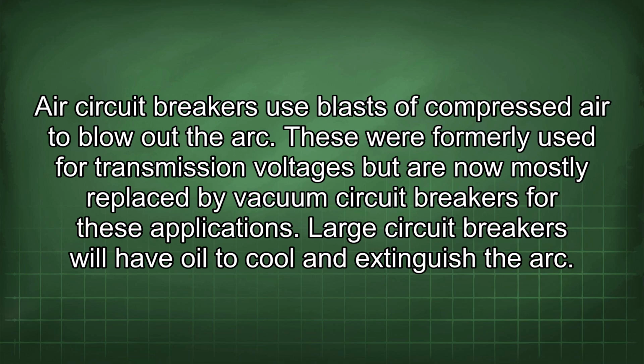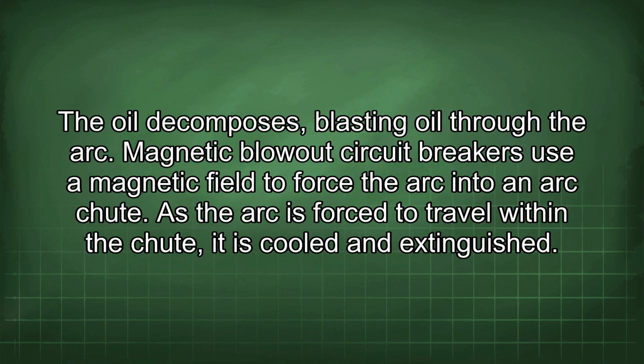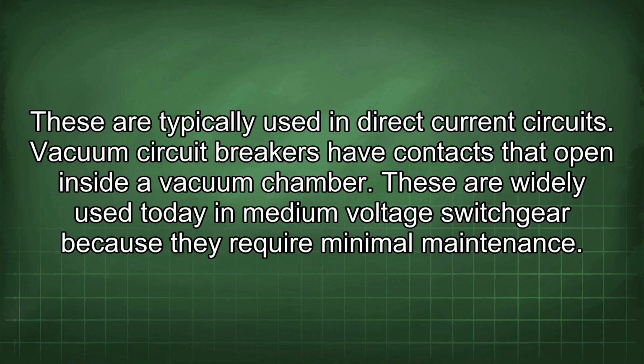Large circuit breakers will have oil to cool and extinguish the arc. The oil decomposes, blasting oil through the arc. Magnetic blowout circuit breakers use a magnetic field to force the arc into an arc chute. As the arc is forced to travel within the chute, it is cooled and extinguished. These are typically used in direct current circuits.